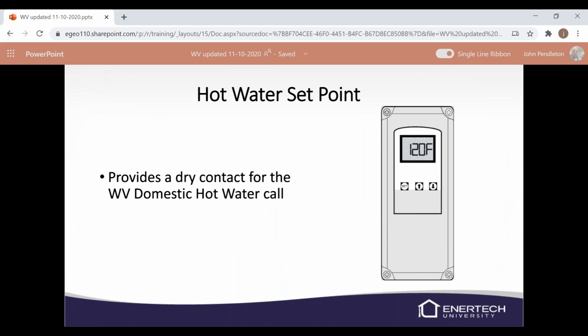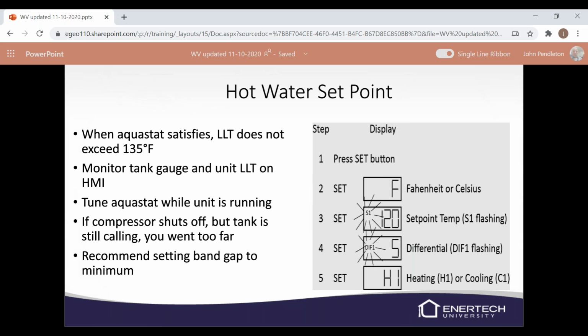Moving on to our hot water set point, basically the aquastat on the tank is going to provide a dry contact for your domestic hot water call. Basically, how we're going to set up the aquastat: if the aquastat satisfies and the leaving load temperature does not exceed 135 degrees. We don't want that leaving load any higher than 135.